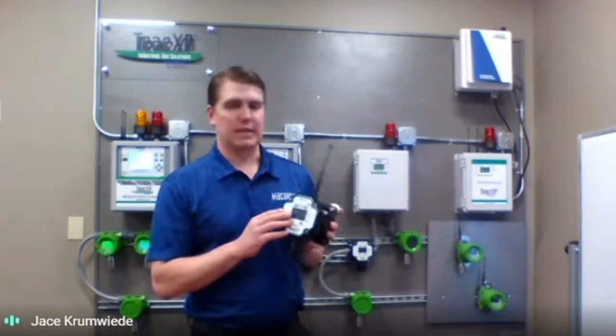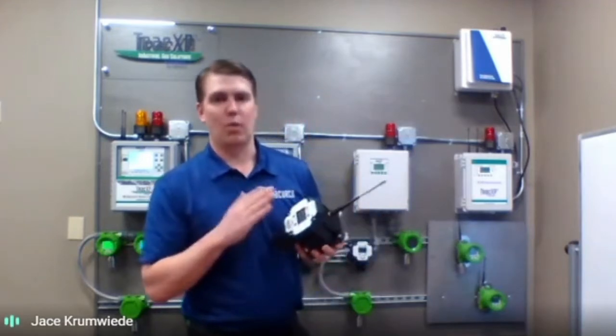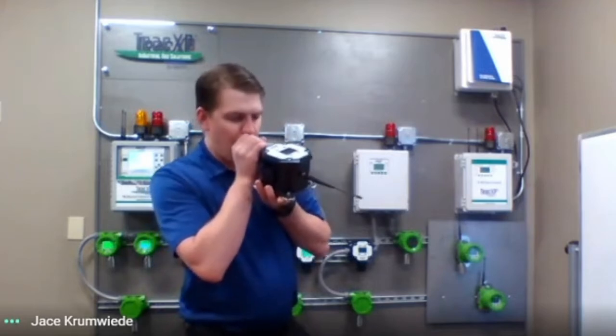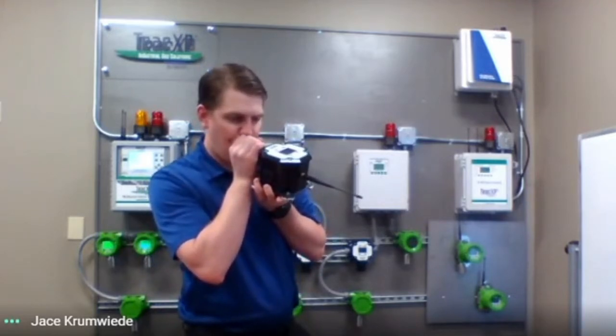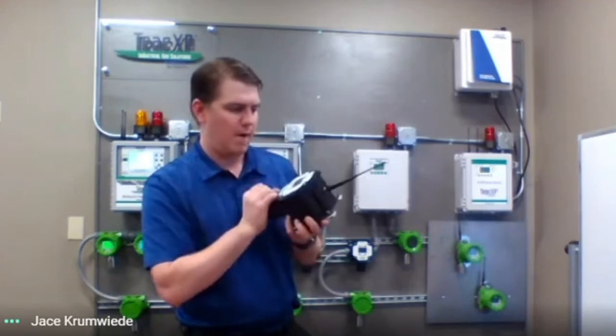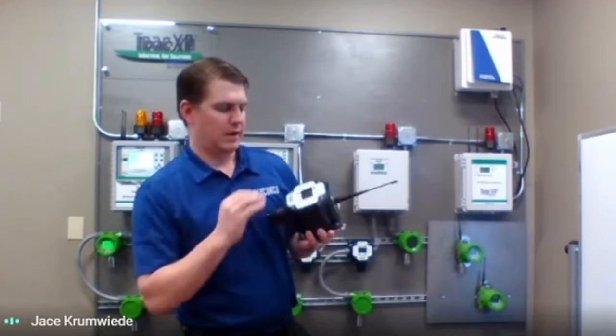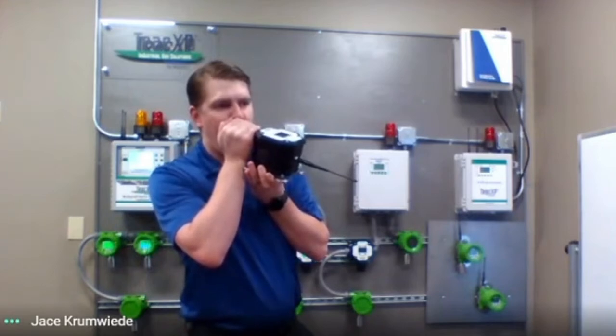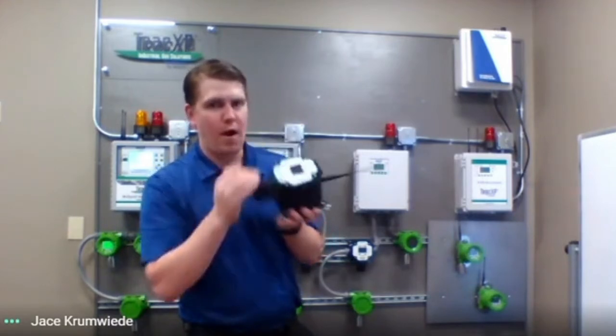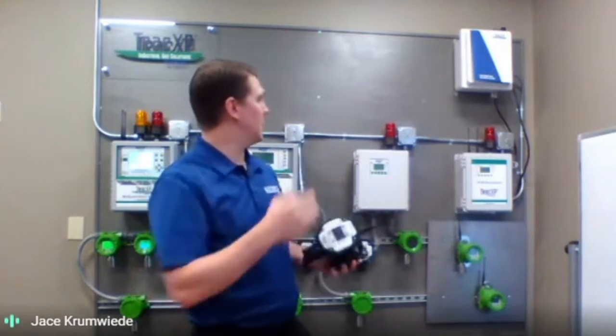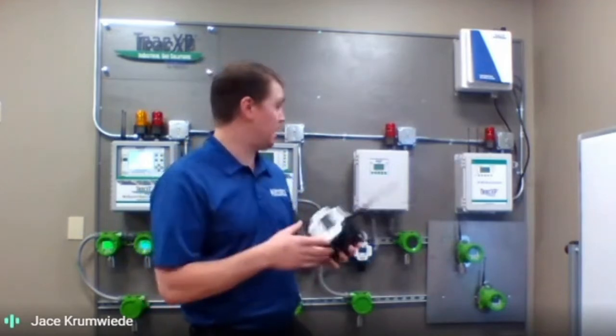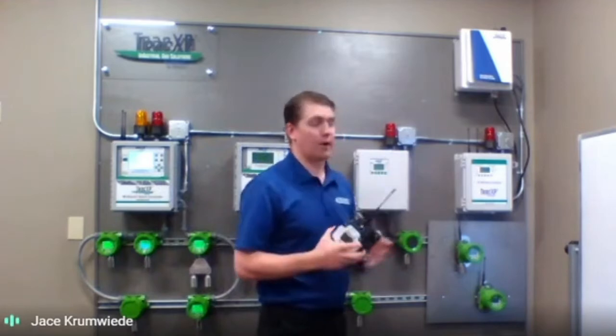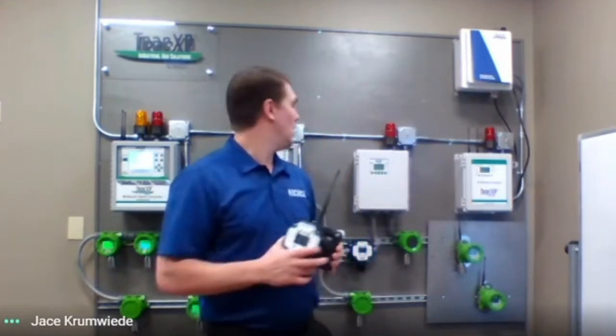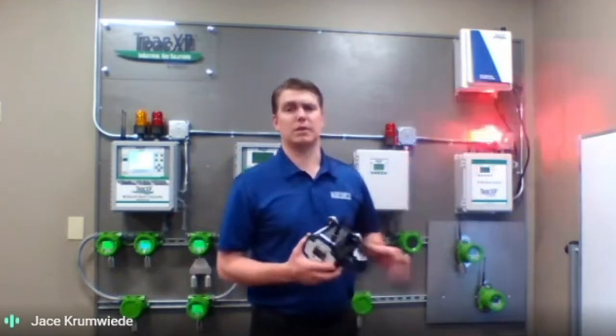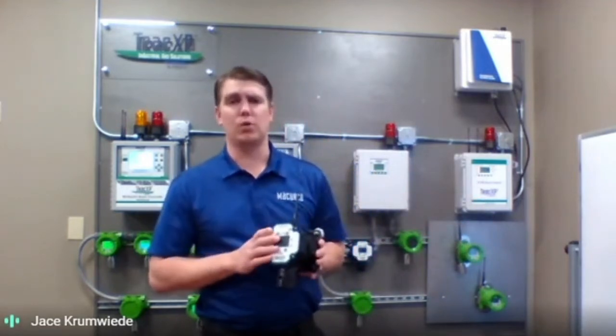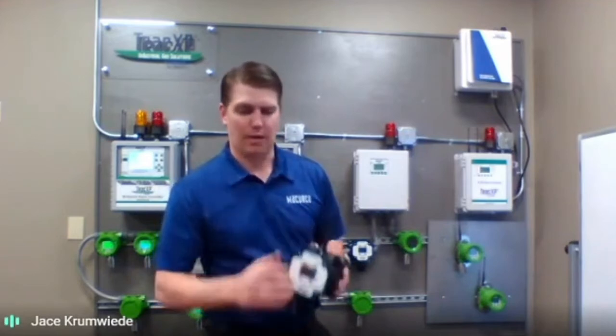This has an oxygen sensor on here, so what I'm going to do again, use the CO2 that I exhale, put it into here, and watch the levels creep down on this one. If I got it down enough. So again, there you go. You got the oxygen levels creeping down to about 15.8% by volume. That's triggering the alarms on the wireless control. You can have up to 32 units connected there wirelessly, and these are single or dual sensor capable.